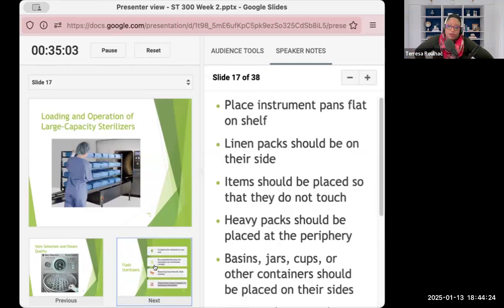But let's say you're at a bigger hospital and you have a bigger autoclave. This is what they look like. You place instrument pans flat on the shelf, like you see here. Linen packs should be on their sides if they had them, but these aren't linen. This is woven, just so you know. You don't want them to touch. If you notice, there are little gaps in between each pack. If you have heavier sets, most likely these ones on the bottom, because you want heavier on the bottom. If there were any basins, jars, or cups, they're also going to be placed on their side.